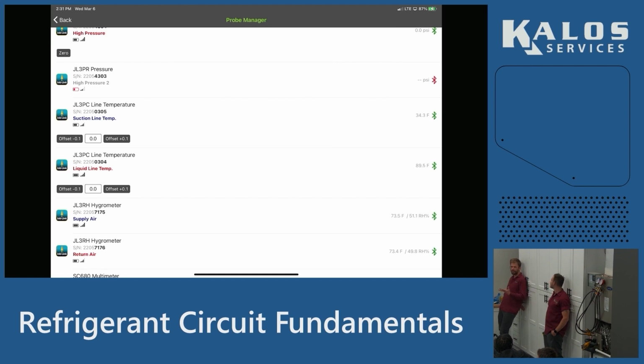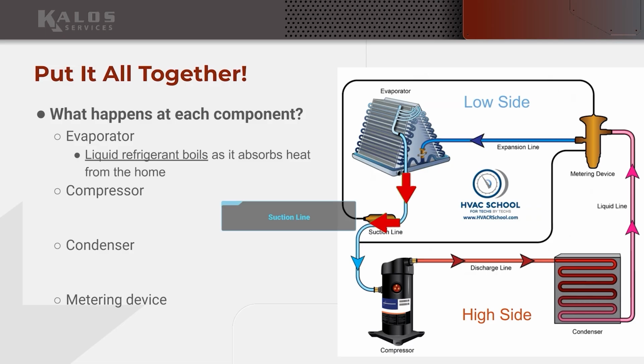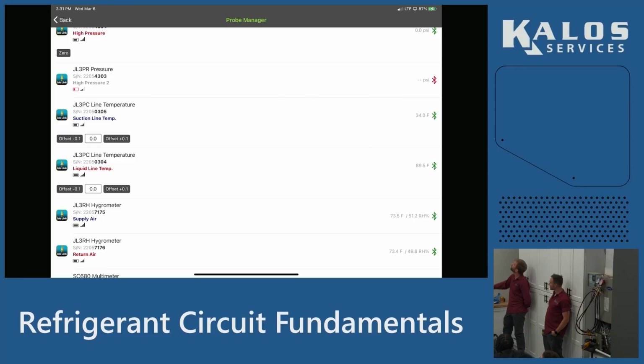That air holds heat. That heat would normally be transferred into that suction line and come out here, but it's not being transferred into that line as efficiently. And so now our suction is 33, 37 degrees. We're almost freezing on the suction line right now. Do you know what's happening outside to our suction pressure?